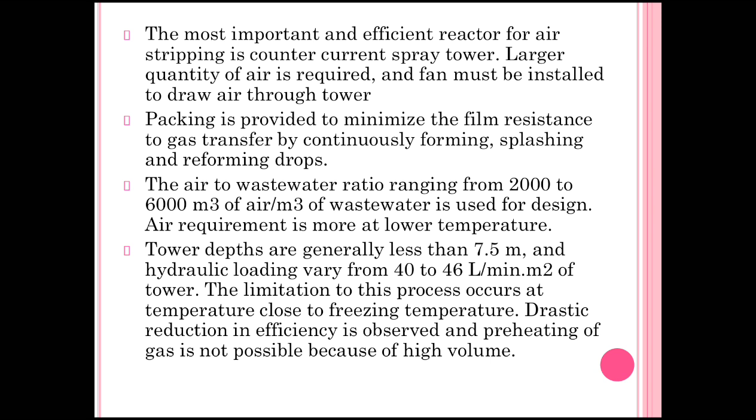The most important and efficient reactor for air stripping is the counter current spray tower. We can see in the diagram that a larger quantity of air is required and a fan must be installed to draw the air through the tower. So the packing is provided to minimize the film resistance to gas transfer by continuously forming, splashing and reforming drops. The air to wastewater ratio ranging from 2000 to 6000 cubic meter of air per cubic meter of wastewater is used for the design.